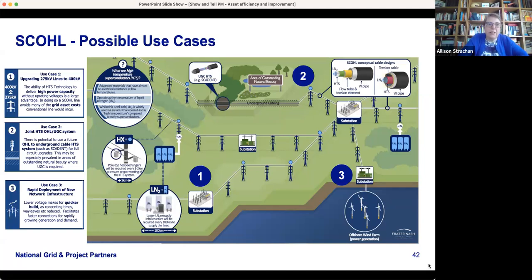The first case, as we've probably already discussed, is upgrading 275 kilovolt lines to 400 kV. Because power density can be increased at 275 using superconducting lines, you're basically increasing the power capacity without uprating the voltage and without making the infrastructure a lot bigger. That's a very big advantage we'll talk about later.